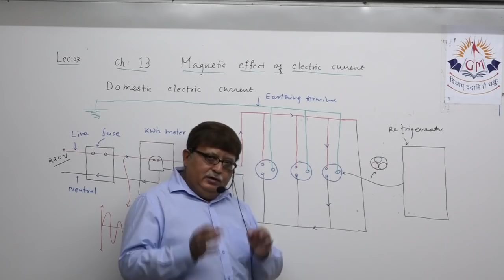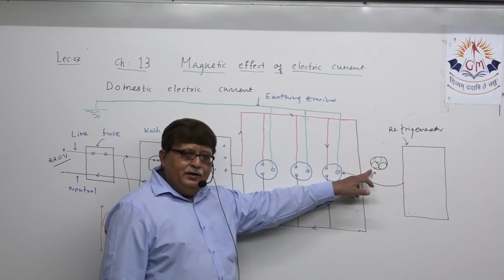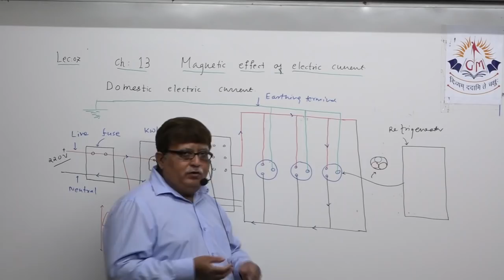So like those students who selected to travel in the path which was not much overcrowded, electric current also, if it abruptly increases, tries to find the path in which it feels low resistance. So what happens? Maximum current flows in the earthing terminal. When these three come in contact, maximum current flows in the earthing terminal, and through the earthing terminal it travels into the earth, and very little current flows in the live wire and neutral wire, which is a safety measure against any short circuit. That's why the importance of the earthing wire is there.